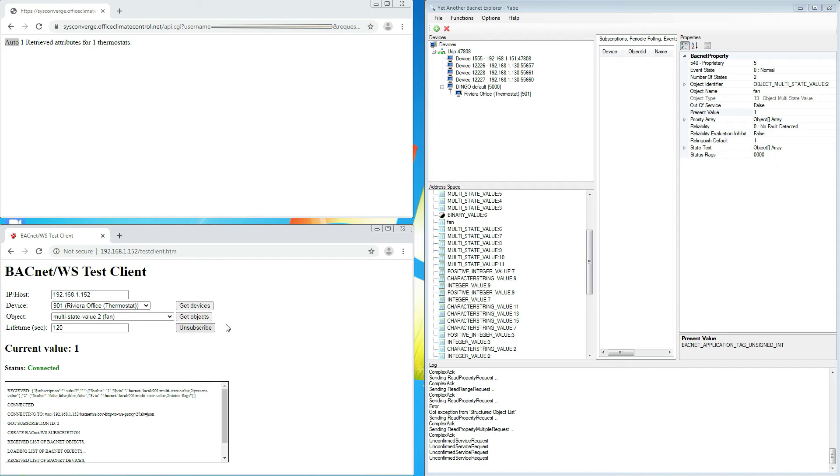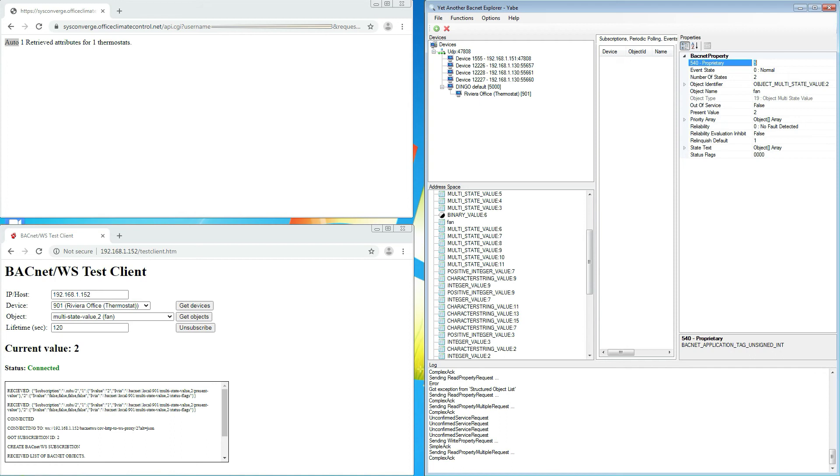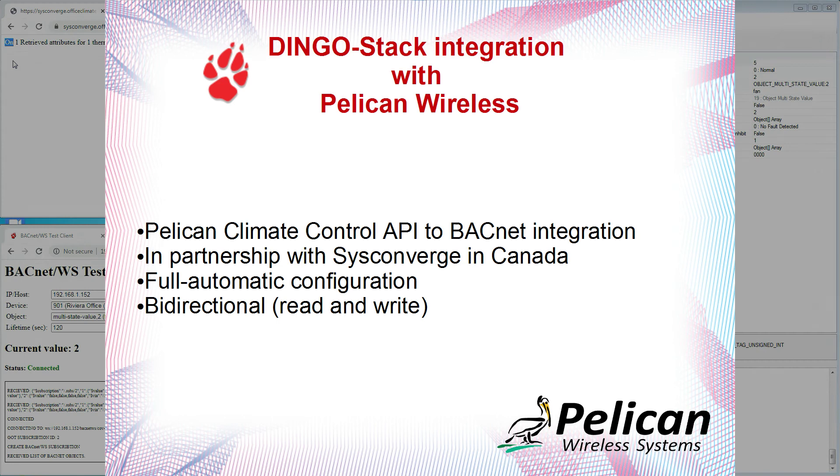If I would change the fan from auto to on by changing the present value from 1 to 2, then we see the value changes in the test client. And if we read the value again in the Pelican API, then we see that it has also changed.